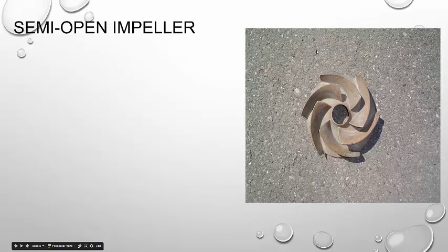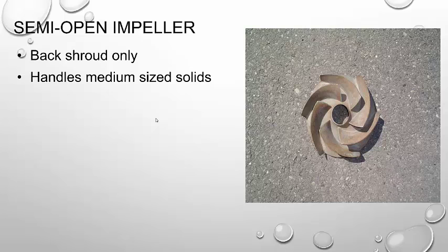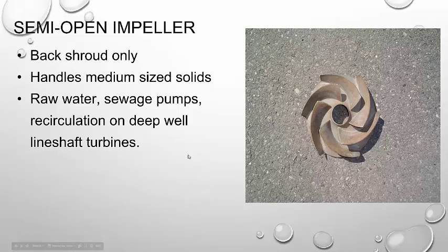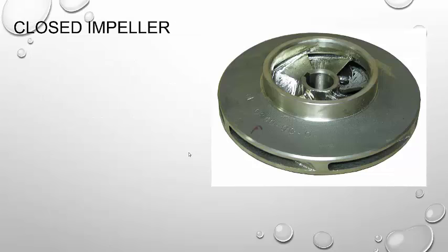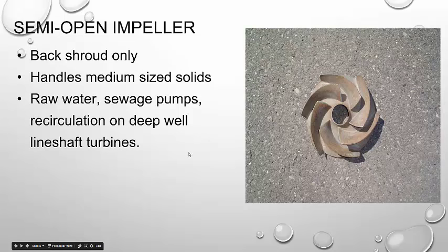And you can see that this should be operating in a certain direction. Why don't you ask yourself right now: should this thing in this orientation in the picture be operating clockwise or counterclockwise? Which way should this be spinning? And remember we're not going to cup the water but throw the water. In this case it should be operating clockwise. Keep that in mind. Back shroud only. This handles medium sized solids because we have some limitation here with the shroud. This is typical in raw water systems, sewage pumps, recirculation on deep wells, some line shaft turbines. Things like that. So that's going to be your semi-open impeller.